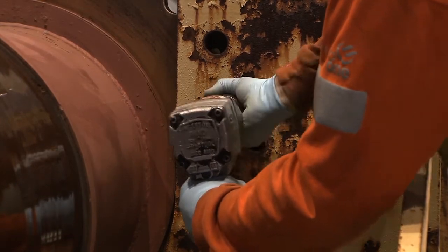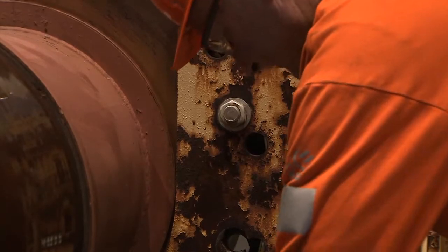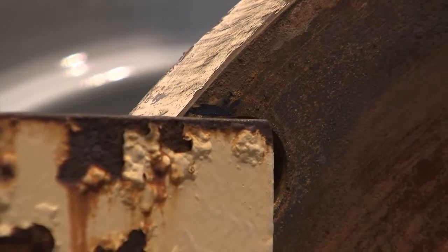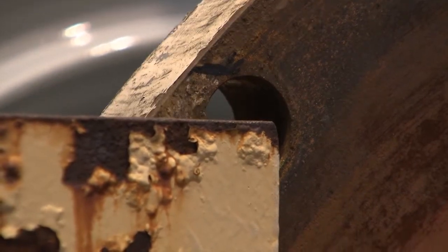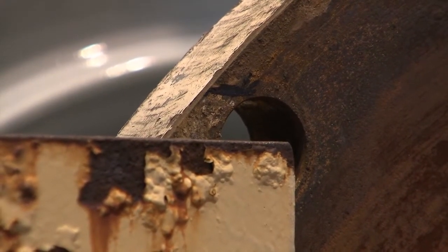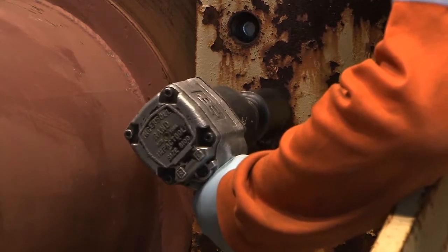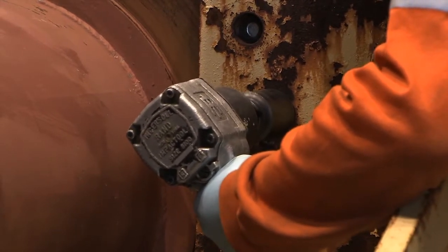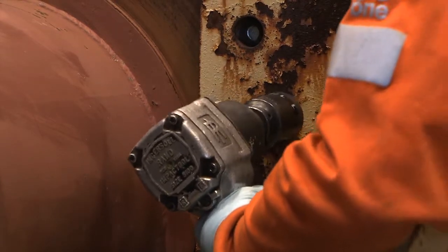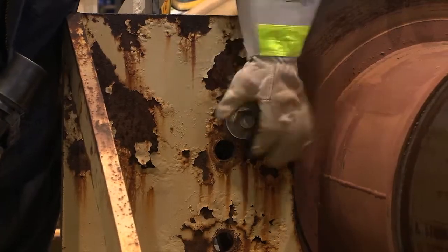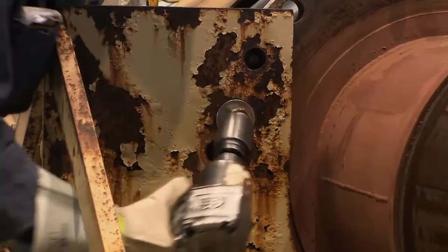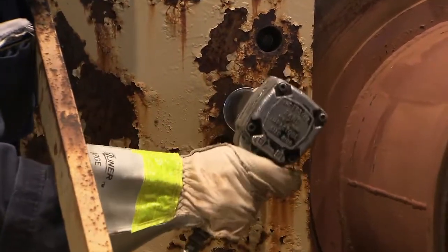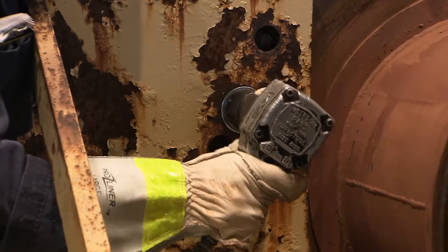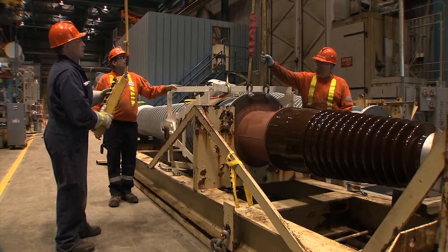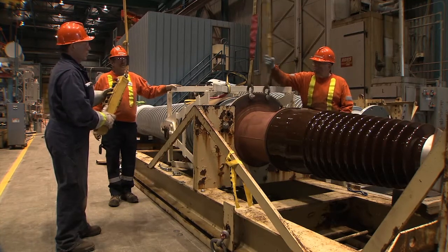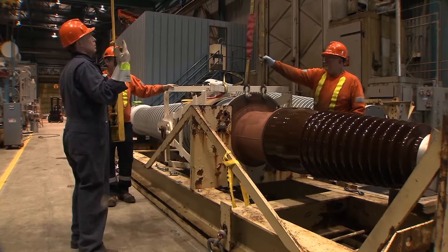Use a pneumatic air gun to remove the remaining bolts that are still attaching the bushing to the carrier. If some of the bolts still cannot be removed, begin to slowly raise the bushing up off the transport carrier to relieve the weight on the bolts that remain. Attempt to remove the bolts again using a pneumatic air gun. Some bolts may have to be reattached in order to equally distribute the weight before they can be loosened. The bushing may have to be incrementally raised in order to achieve the proper weight distribution to remove the bolts.